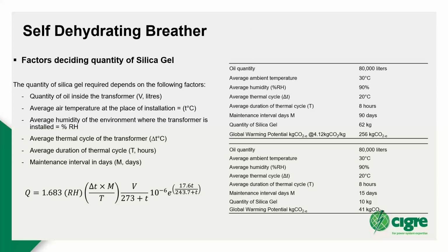When we talk about how we decide on the quantity of silica gel, that's predominantly determined by the quantity of oil inside the transformer, the average air temperature at the place of installation, the relative humidity, the duration of the thermal cycle, and how often you maintain it. So the quantity of silica gel is directly related to the maintenance interval.